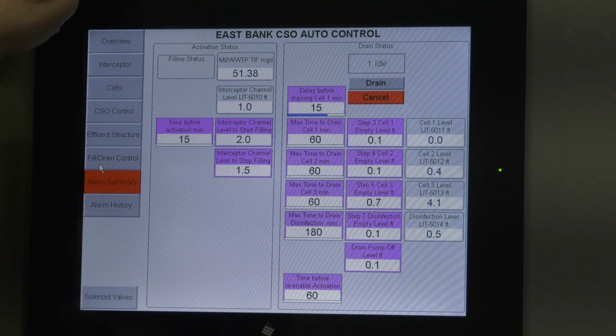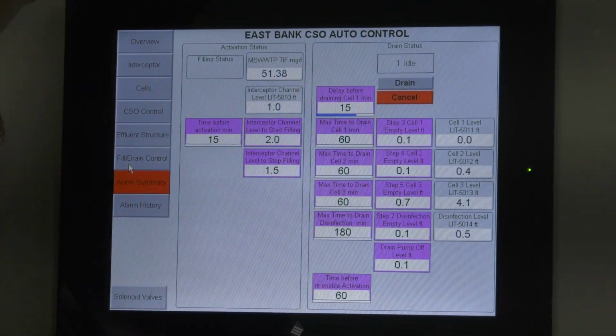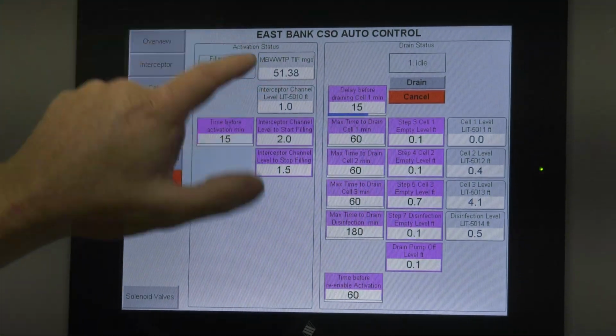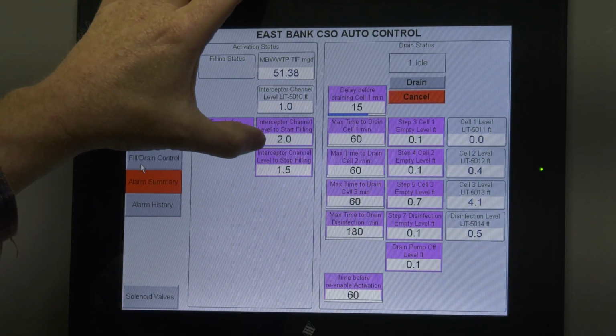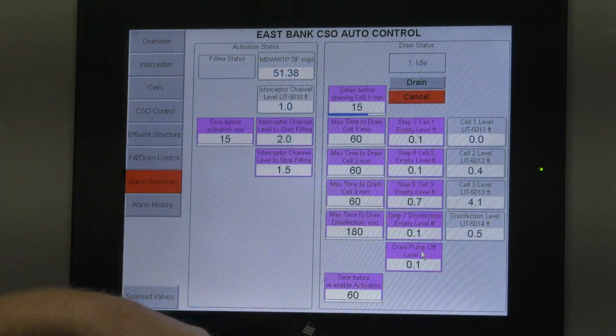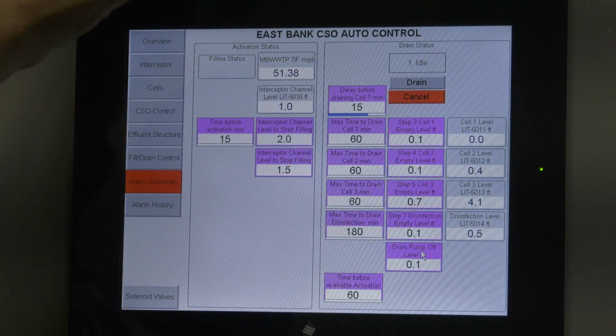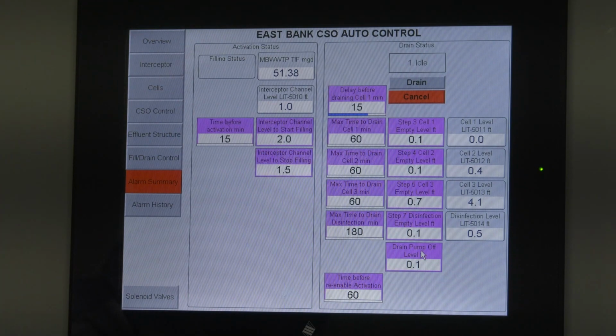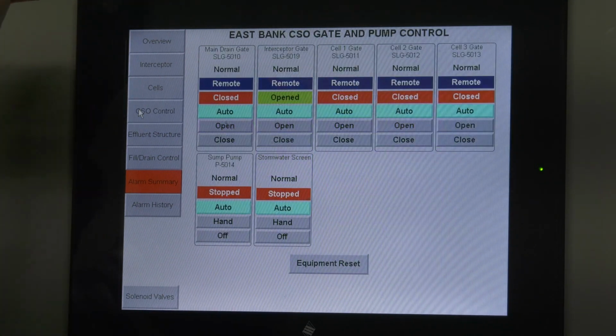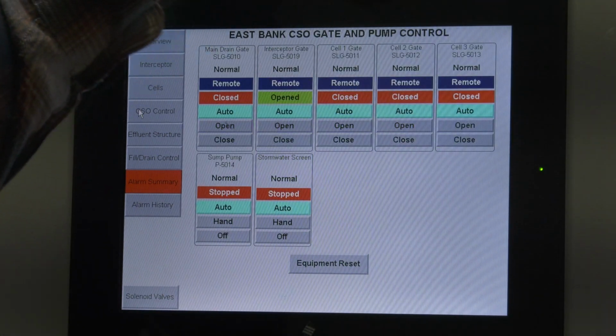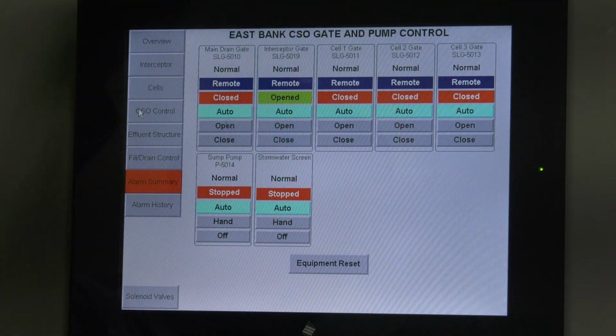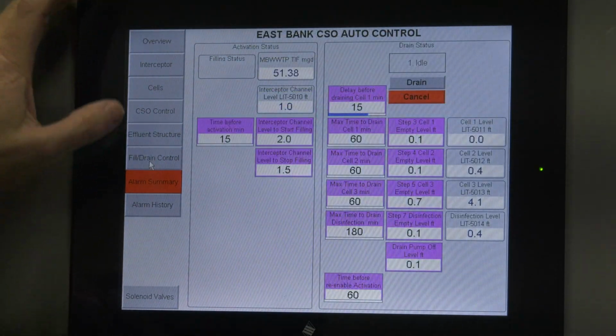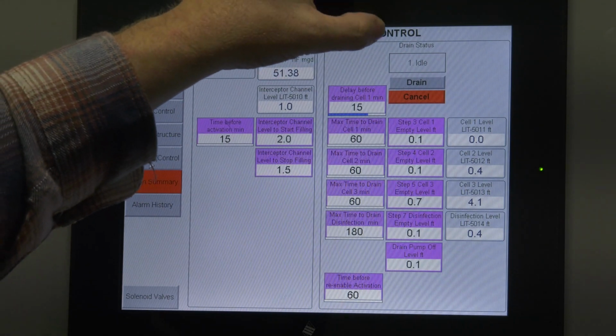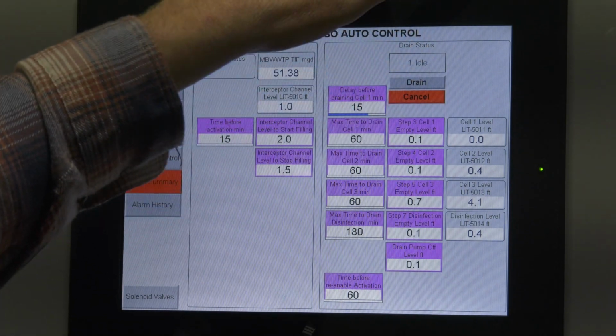Fill drain control. To initiate a fill cycle, you set the interceptor level, start filling at operator adjustable set point, and a stop filling. If it's in between those two levels, you're going to be automatically filling. You've got to have your valves or your gates in automatic mode. To drain, you press the drain button. It'll initiate automatic drain sequence.